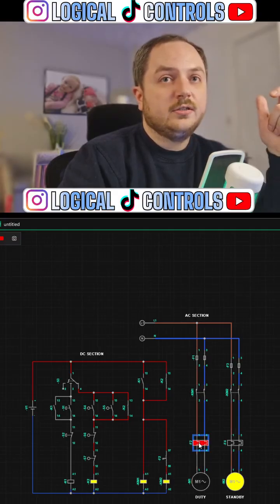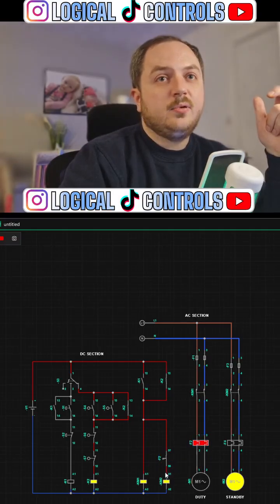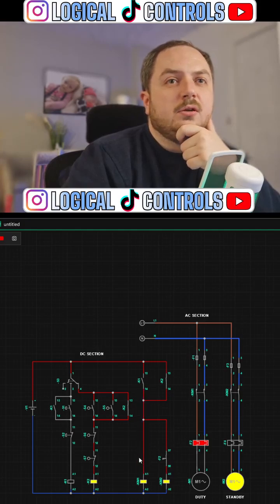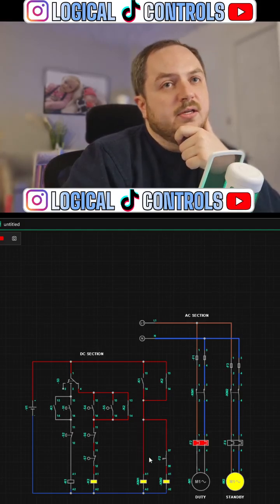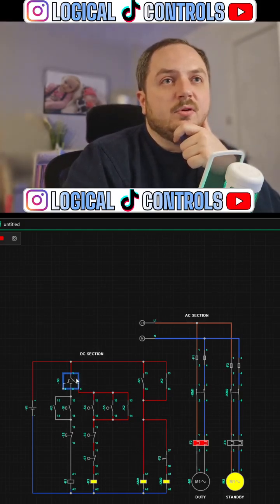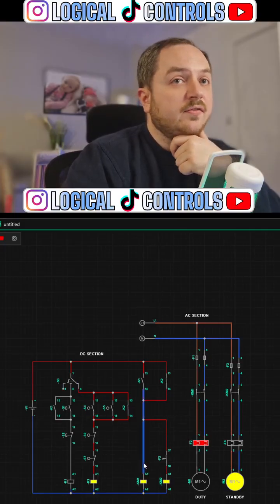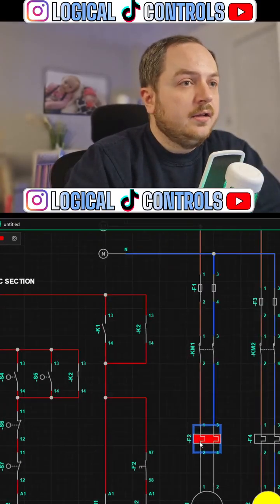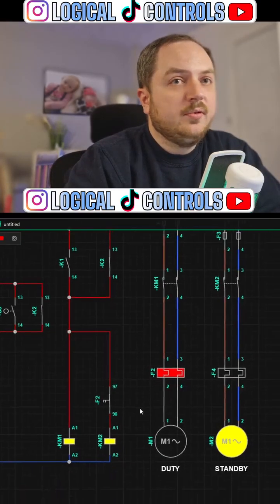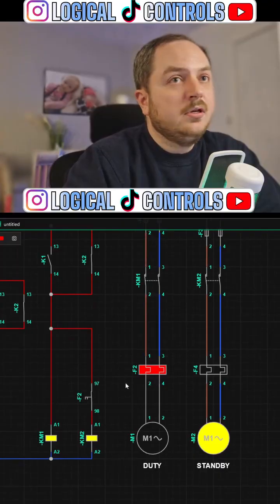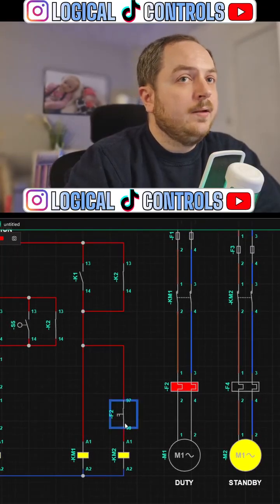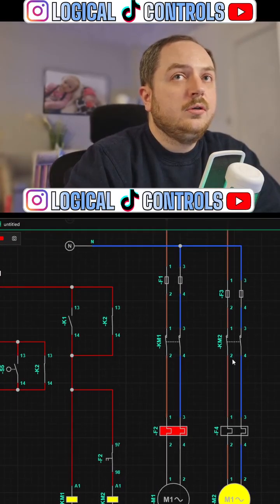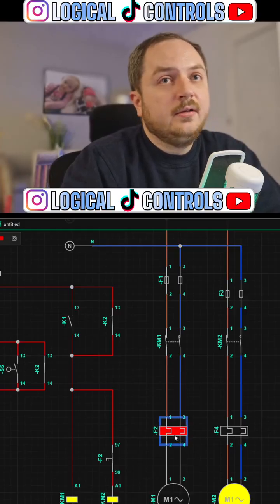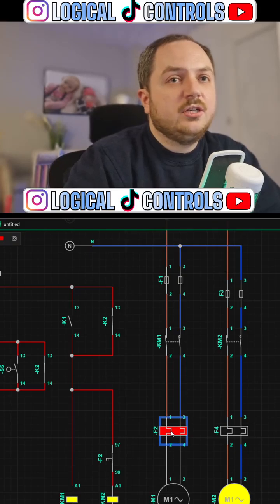And if the overload triggers, then at that point, should I have put a normally closed in there? Possibly. I probably, in fact, I should have probably put, yeah, maybe I should have put a normally closed in there, off F2 as well. Anyway, F2, the overload for that pump, the duty pump, tripped out. An auxiliary contact then brought in KM2, which is the contactor for the standby. If I was to put F2 back off again, I think it would just change back over.